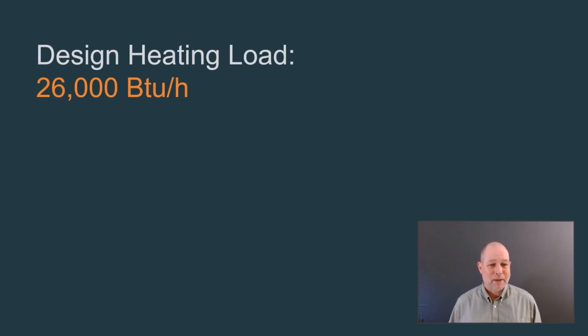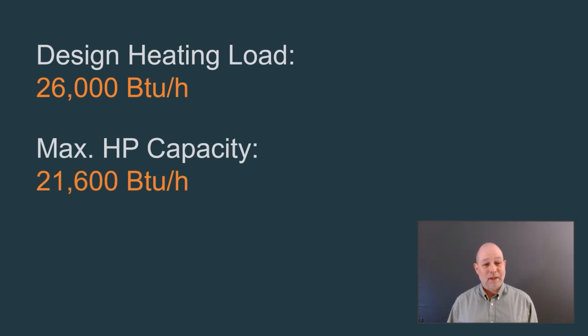Because I'm a geek, when I visited my friends once, I calculated the design heating load for their home. Not a big deal, probably took half an hour. I came up with a design heating load of 26,000 BTUs an hour. If I look at the maximum capacity of that heat pump at the design temperature of 5 degrees Fahrenheit, the maximum heat capacity is 21,600 BTUs an hour - considerably less than the design load.